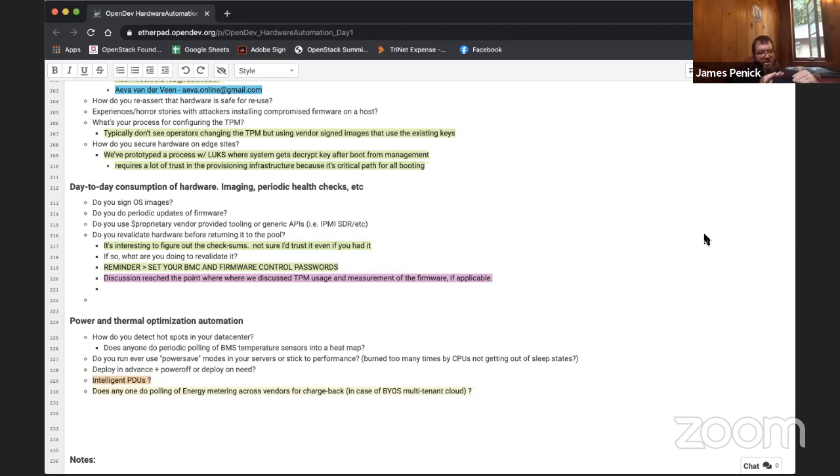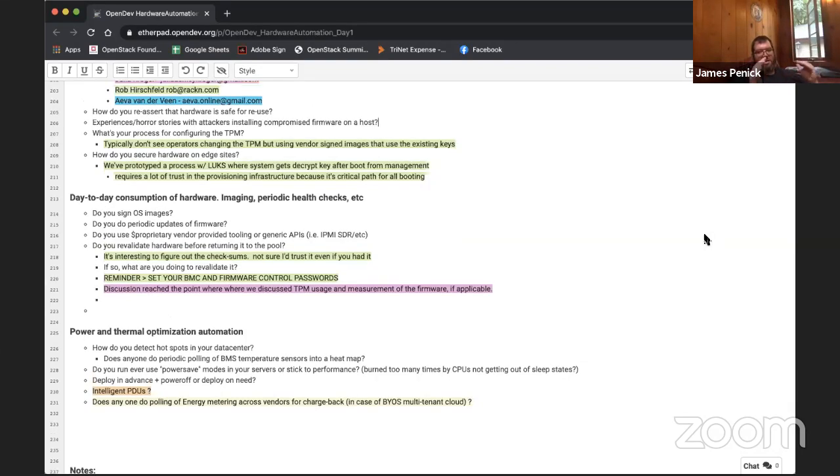So there's some automation that our site ops automation team, our data center automation team, has, that goes through and examines the thermal state of the data center. There's lots of really cool stuff happening that's controlling it. The louvers are all automatic, and there's a whole control brain to the whole thing. But in addition to that, this site ops team automatically monitors when one of these pods has too many servers turned off, and will actually turn some back on just to act as those passive fans and help balance the cooling in the data center. So it's interesting that we manage cooling in our data center partially by turning machines back on.